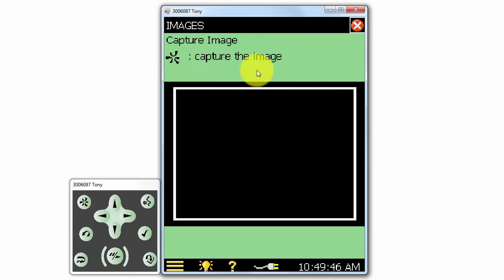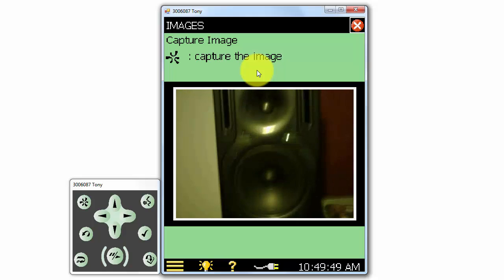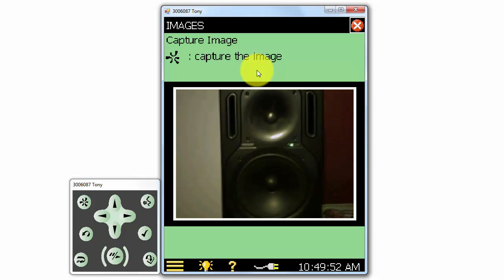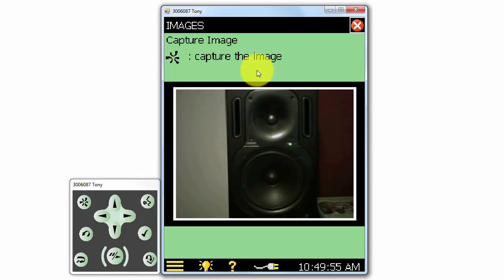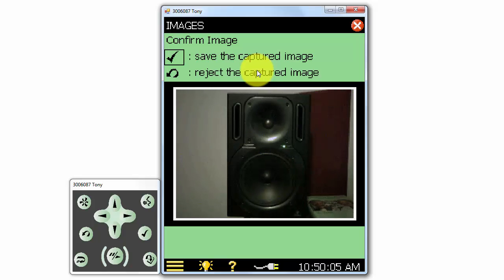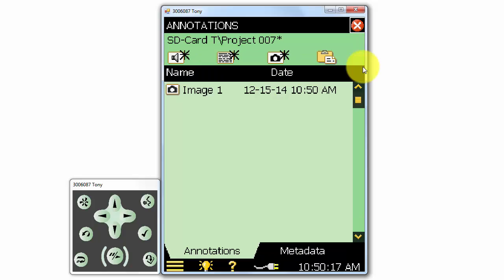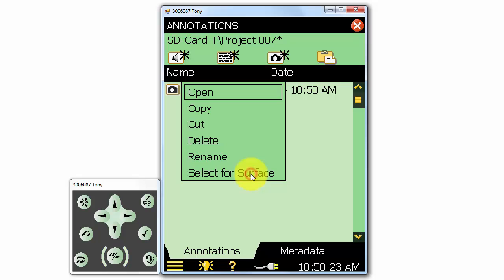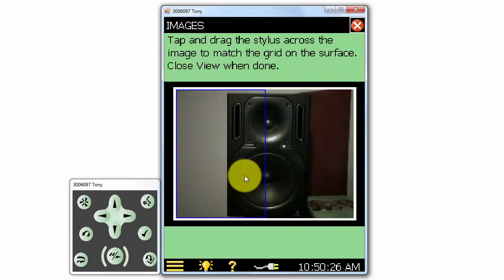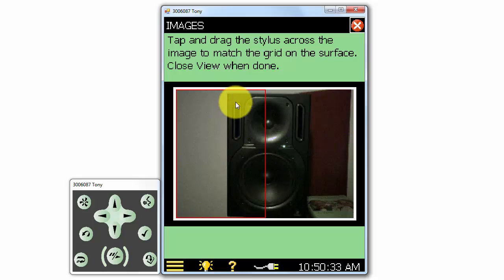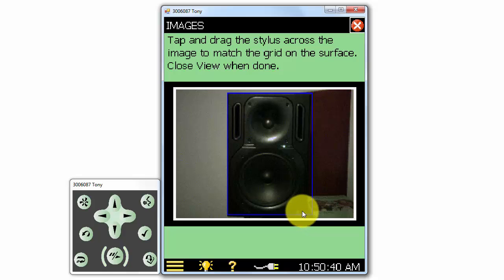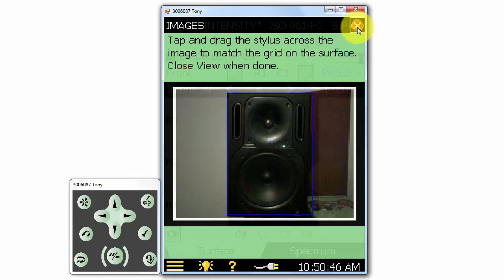I'll go ahead and do that. The camera view is displayed on the meter screen, and I'll line up the speaker in the viewer. I'll click the Manual Event button to take a picture, and then the Confirmation button to save the image. When we have the image saved, we can specify which portion of the picture is related to our measurement surface by dragging the stylus on the screen to mark which portion will be used. When we close the window, we can see that the picture is now shown in the Surface tab for the selected measurement surface.